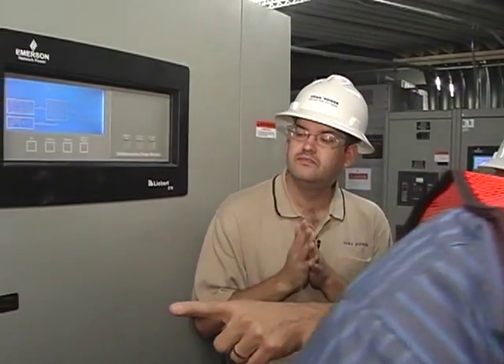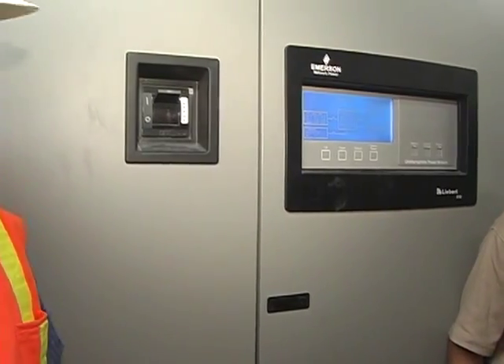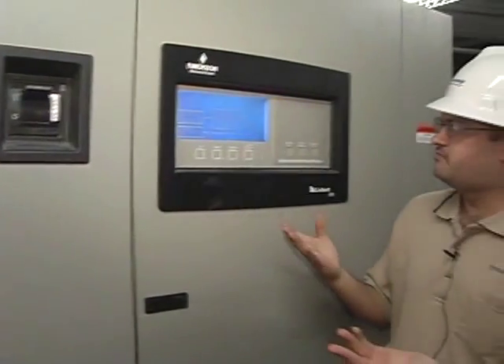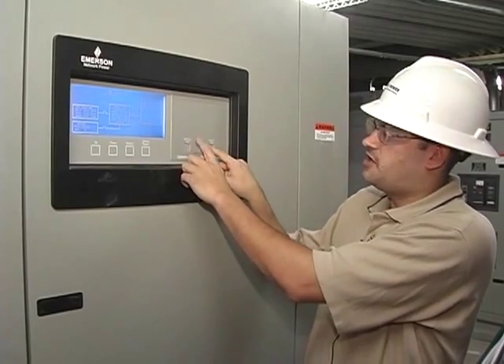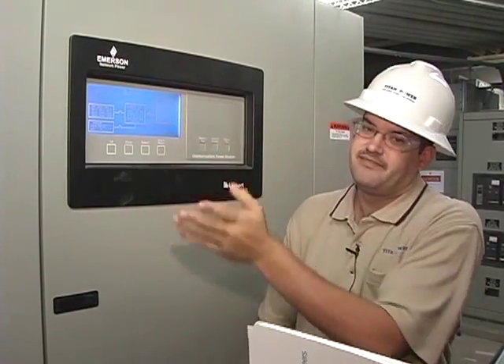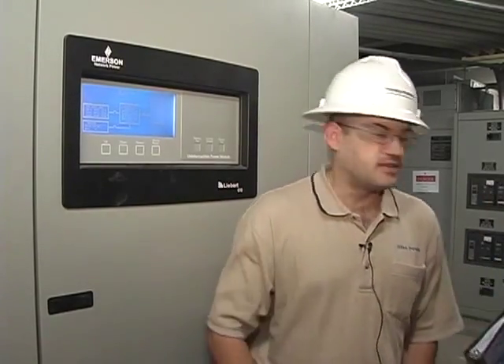We've got the UPS input breakers. The battery breakers are in that big gray cabinet right there, and that's identical for both UPSs. If you ever need to trip them for shutdown, just follow the procedures — it's control enable, output trip to trip that one; control enable, battery trip to trip your battery. If you've got an alarm and everything still seems to be working, press the alarm reset button and if it's not anything major, press the alarm reset and it'll go away. They also have an EPO button.